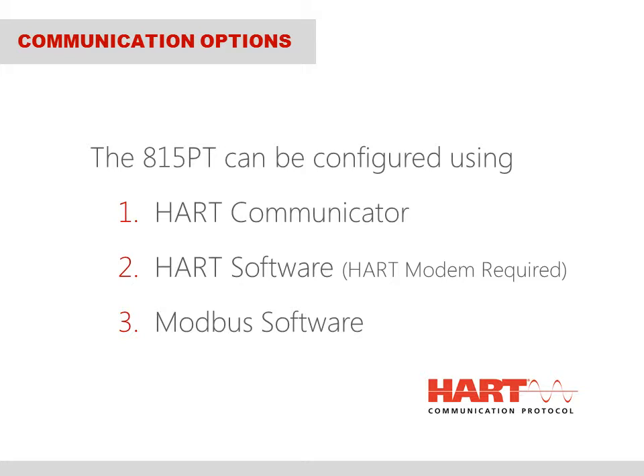Lastly, any supervisory control system with Modbus configuration software, which could be a laptop and an RS-232 to RS-485 converter module. The Modbus software and converter module are also available from many suppliers, and as with the HART modem, the converter module plugs into a standard USB port.